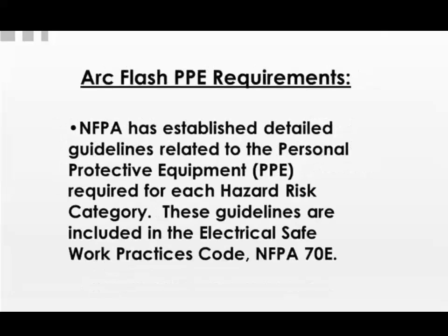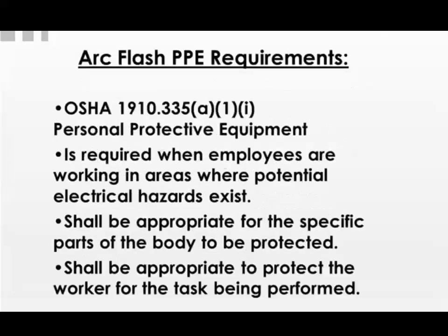Now, arc flash PPE requirements. The NFPA has established detailed guidelines related to personal protective equipment required for each hazard risk category. The hazard risk categories are important to know. These guidelines are included in the Electrical Safe Work Practices Code of NFPA 70E. OSHA also requires PPE to be worn under OSHA 1910.335(a)(1)(i). 1910 is general industry. As a side note, OSHA has two standards, general industry and construction. If you ever see OSHA 1926 or CFR 1926, that is talking about construction. This particular standard falls under general industry, personal protective equipment.